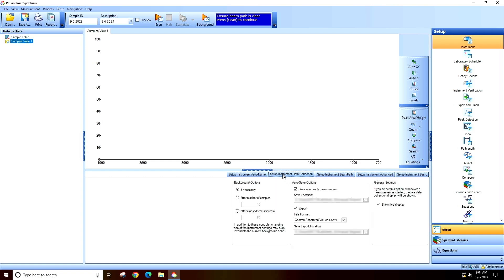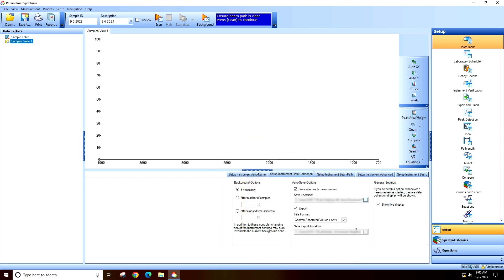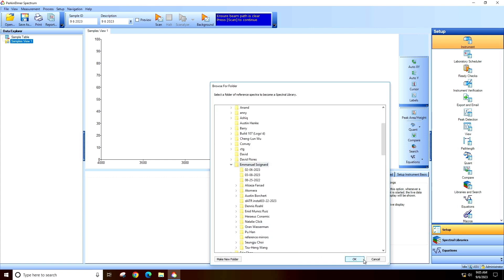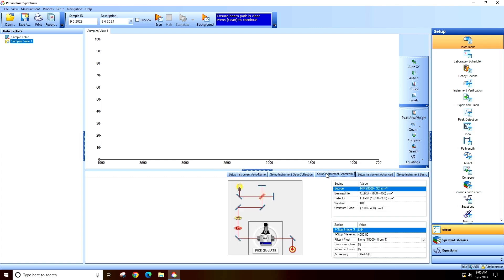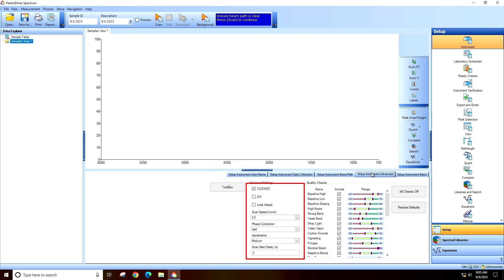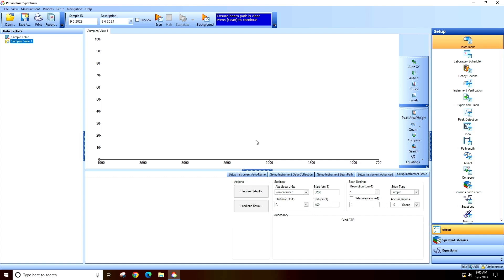In the Setup Instrument Data Collection tab, select your folder for both the Save location and the Export location. Check the settings in Setup Instrument Advanced. Finally, select the appropriate ordinate for your data, the start and end wavelength, and the appropriate number of scans for your sample.